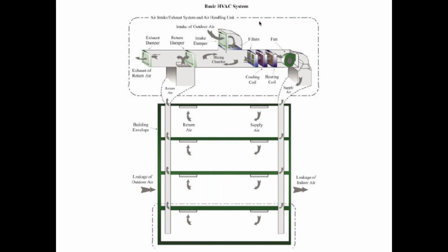My guess is that most of this is probably part of the central unit, and that may be part of a second air handler that's separate from this. So at any rate, what would we expect to see here? What we would expect to see in the air handler is a fan to make this whole thing work, a big one, right? And then what else would we expect to see? We would expect to see a coil to cool the air. That coil could be using Freon, not necessarily. We'll get to that in a second.